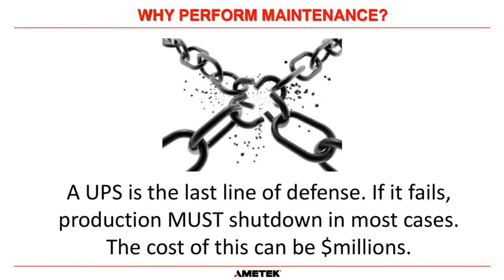And of course, why perform maintenance on a UPS? Well, the UPS is the last line of defense. A UPS is always connected to absolutely critical loads. That's the inherent design of the system. And if the UPS fails unexpectedly, in most cases, unfortunately, the production of the unit must be shut down. And that cost can be millions of dollars.